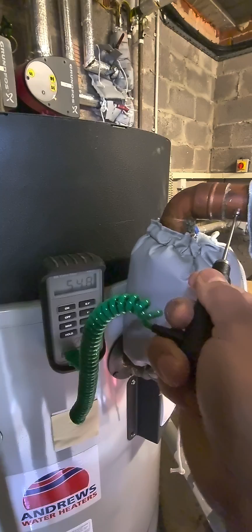So the temperature of the flow is 62.7. Normally the temperature of the flow should be more than 60 degrees Celsius. So 62.7 is fine. So I'm going to take the temperature reading for the return.